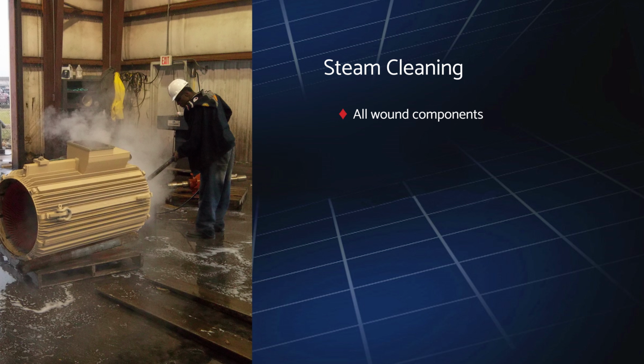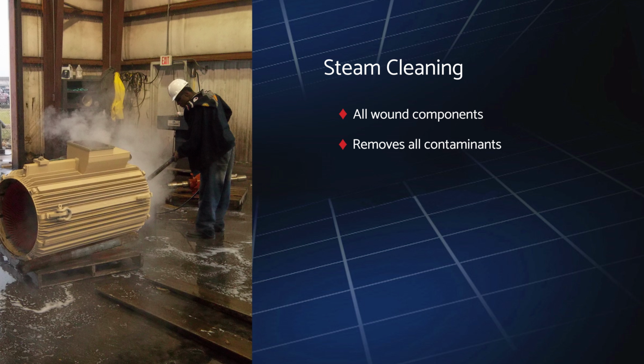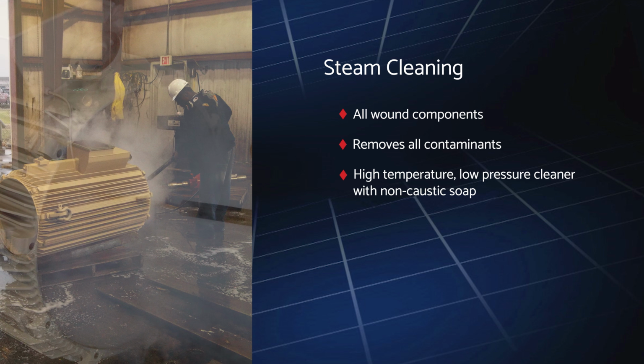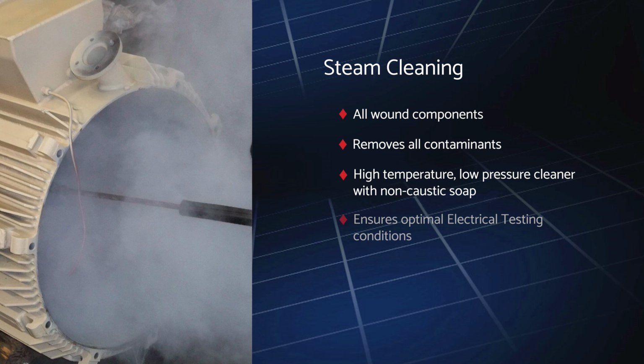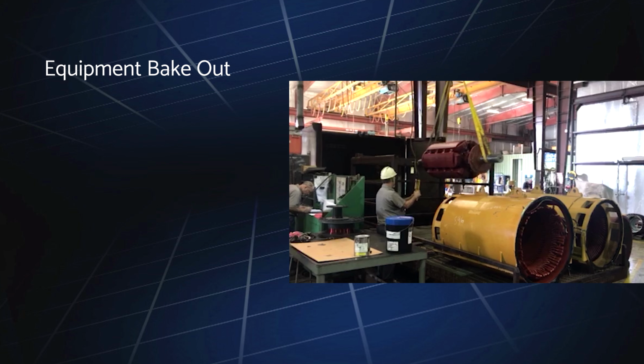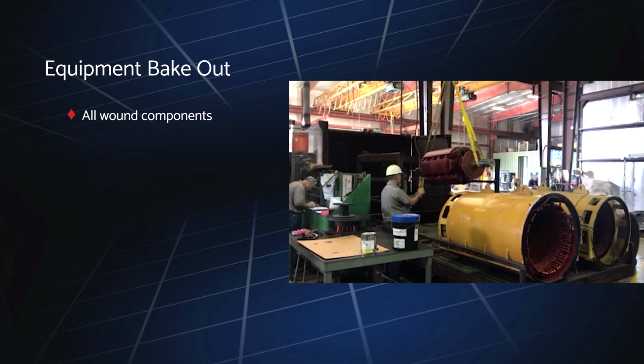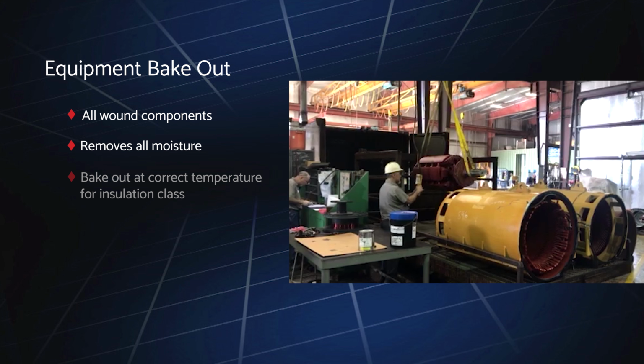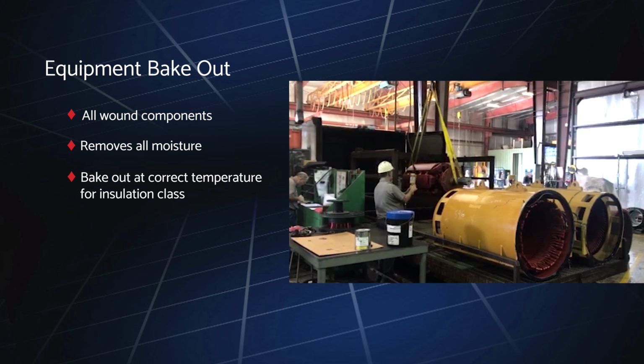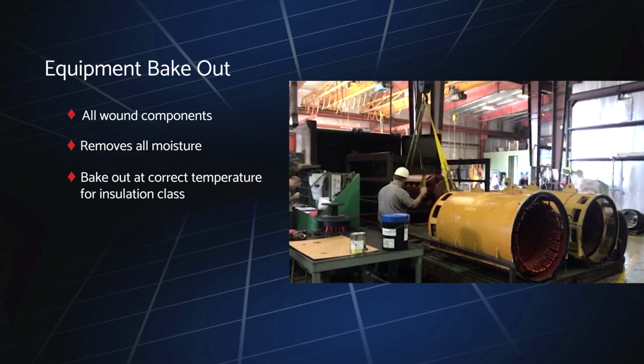All wound components are then steam cleaned in our dedicated cleaning area to remove all contaminants using a high temperature, low pressure cleaner with non-caustic soap. The wound components are then baked out to remove all moisture at the correct temperature for each insulation class, which ensures optimal testing conditions.